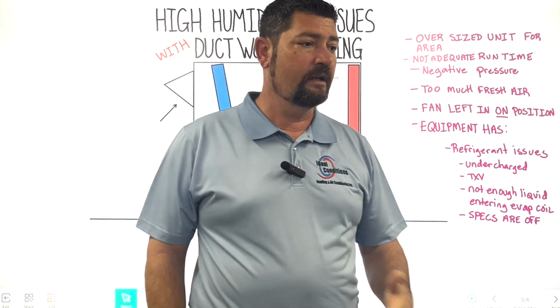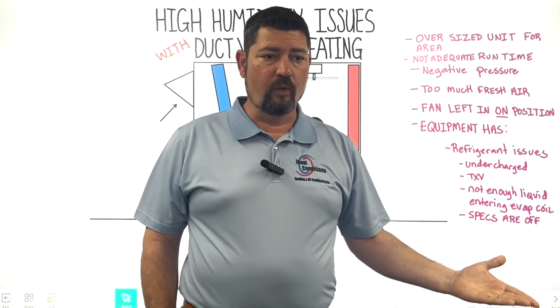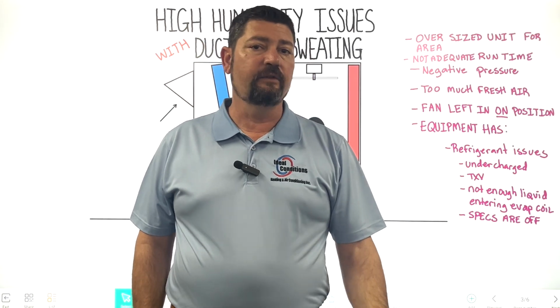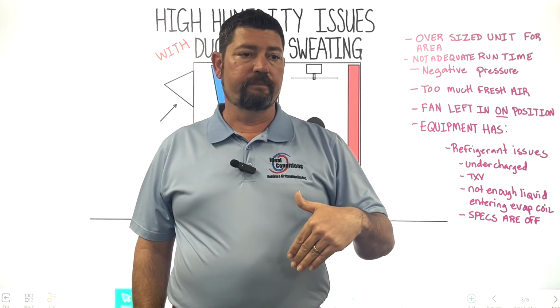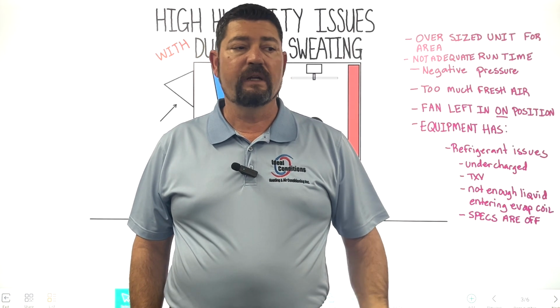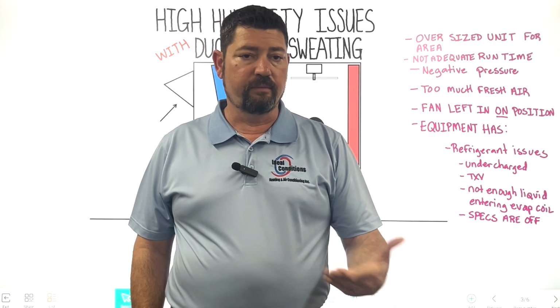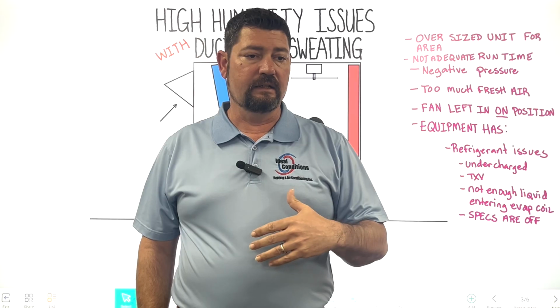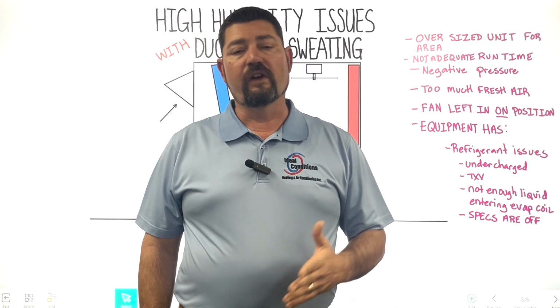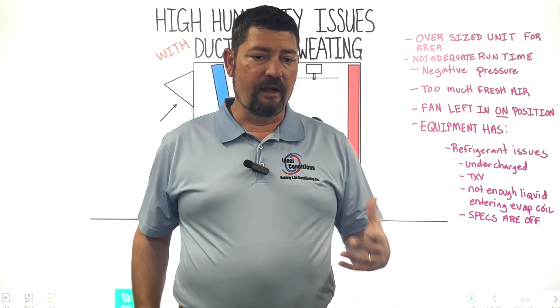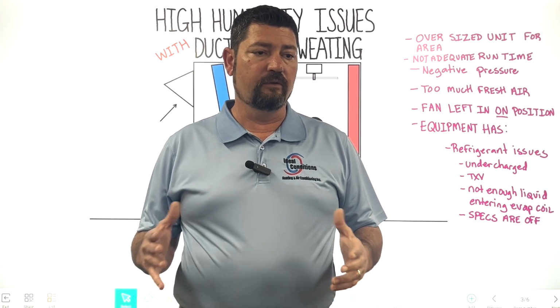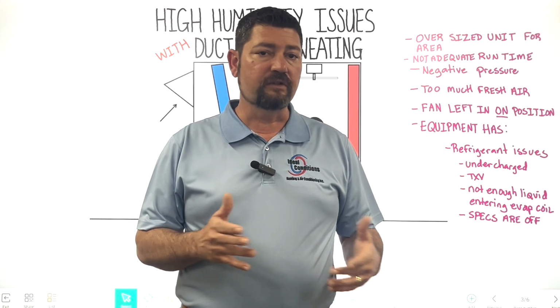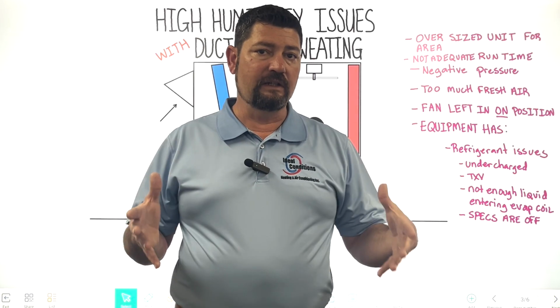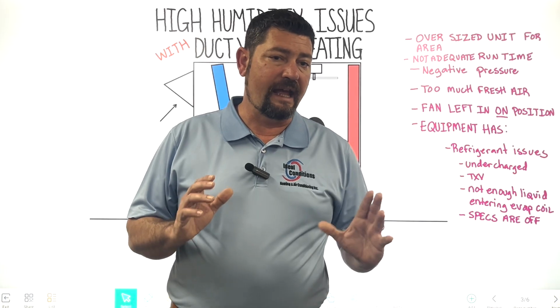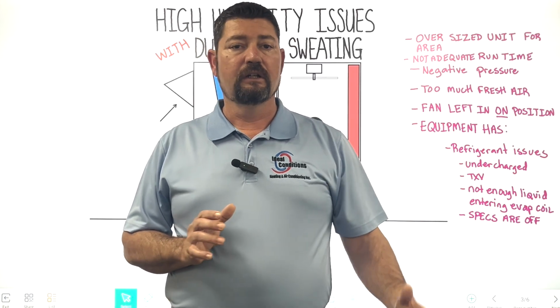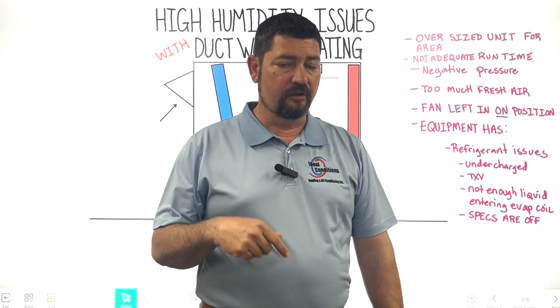We see this a lot to where maybe the tenant that was in there before, maybe it was a restaurant, had a higher heat load, so maybe there were more air conditioners in place, or maybe they had just a high heat load in general. Maybe there was a large office requirement for people and equipment that was putting out a lot of heat, and they just upsized the RTU. That's very typical. We have to find a healthy balance so we don't go too crazy with these RTUs. Meaning, if we have a 5-ton and you require a 10-ton, sometimes it's better just to not put a 10-ton RTU on it. Maybe keep a 5-ton there, and then maybe add a 5-ton split system to the building. We've done that a lot of times just for this reason.